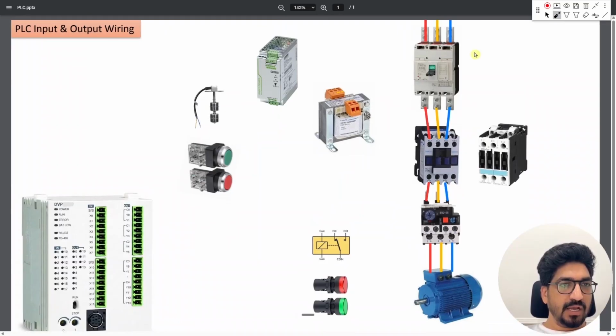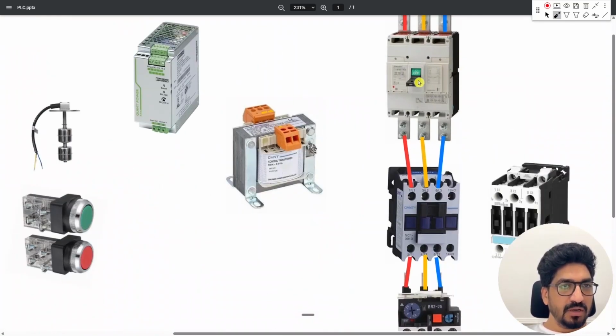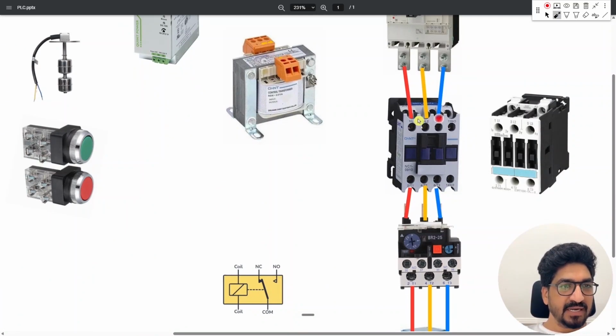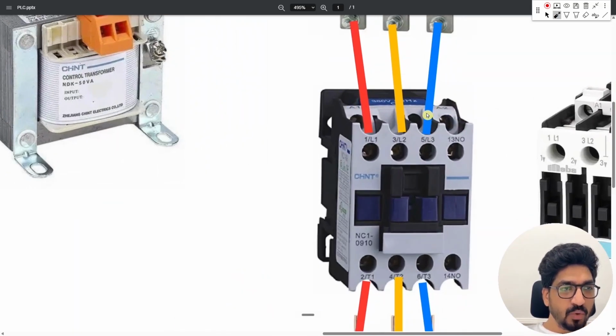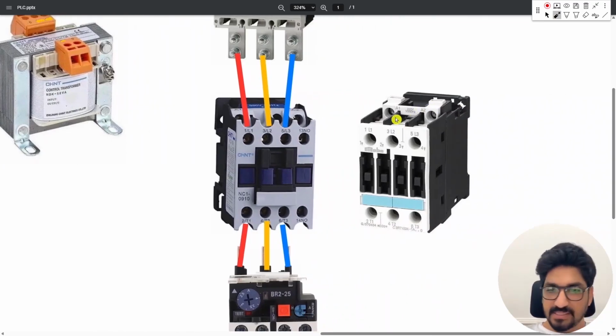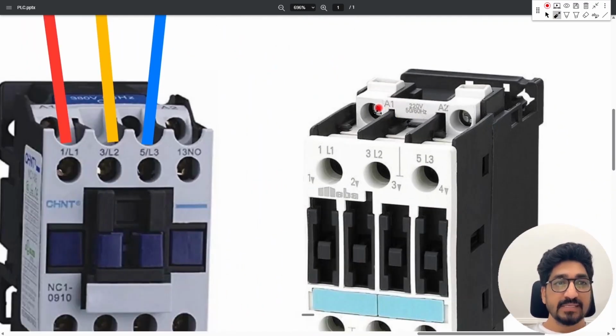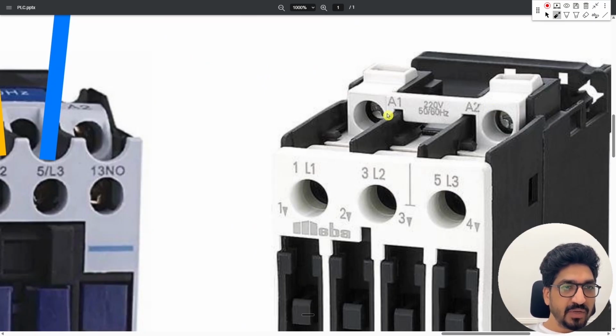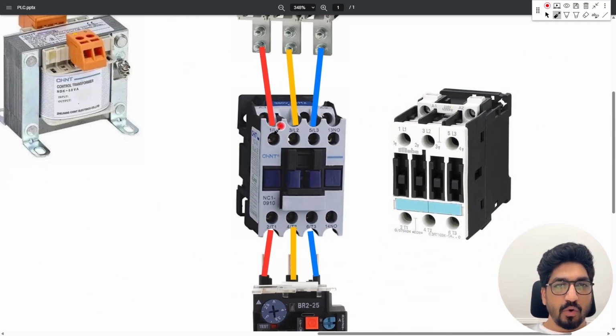So how does this work? When you switch it on, power is available at the input of the contactor, which is a three-phase switch controlled by a coil inside. Where is the coil current coming into? The coil current comes into A1, A2. In this picture you can see two more terminals inside A1, A2, working on a lower voltage, let's say 220 volts. These three are 440 volts. This is a single phase 220 volt to power the coil inside.